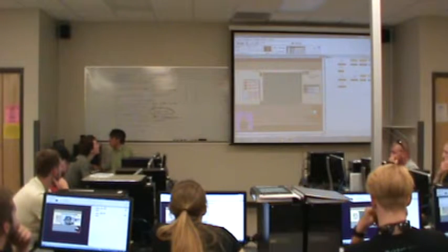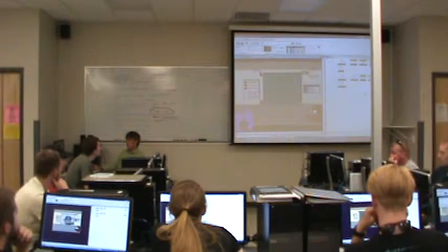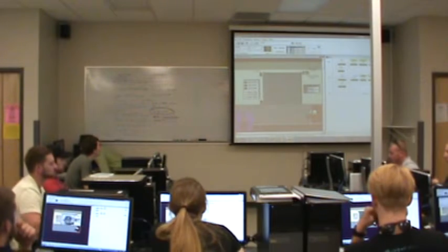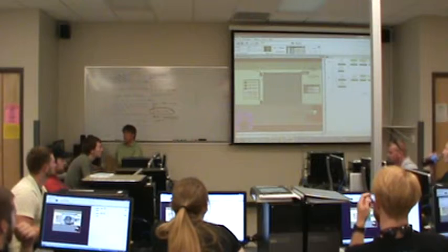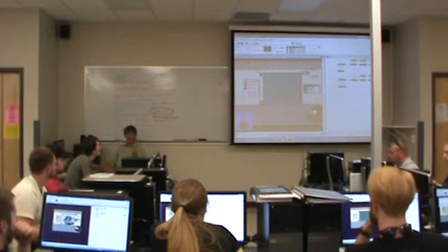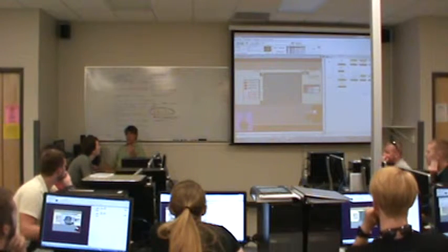We've got the open, the close, and the stop buttons working, and we're not burning up the motor anymore, but it would be nice if the ajar, open, and shut lamps would work. Okay? So let's make those function. In fact, we like the open lamp to be on solid when the door is open. When the door is opening, we would like for the open light to flash.